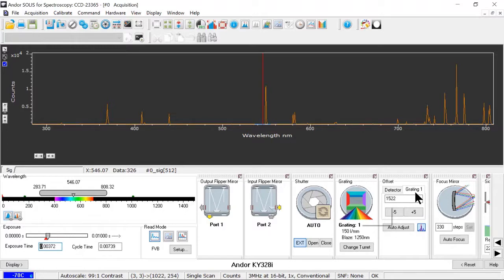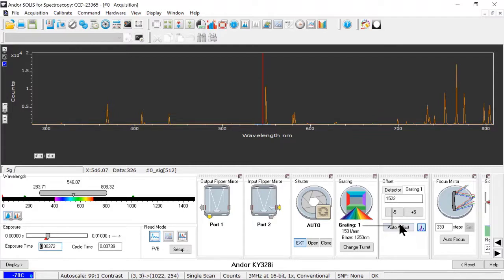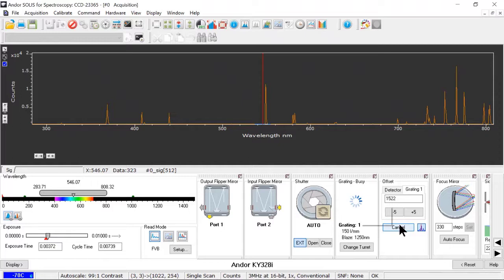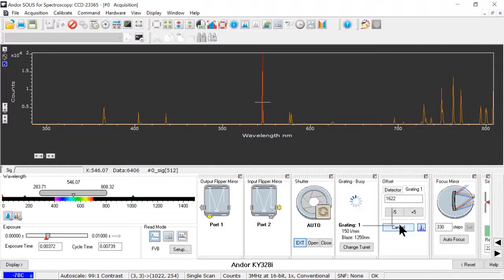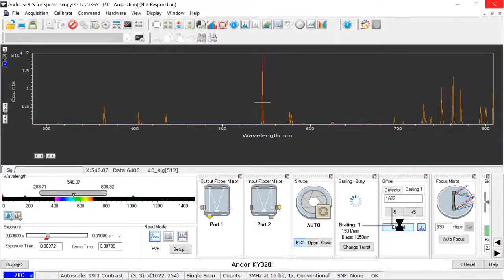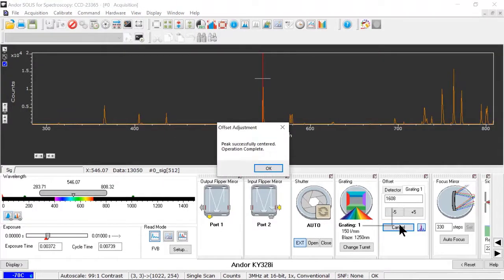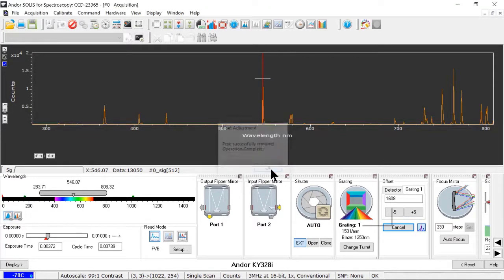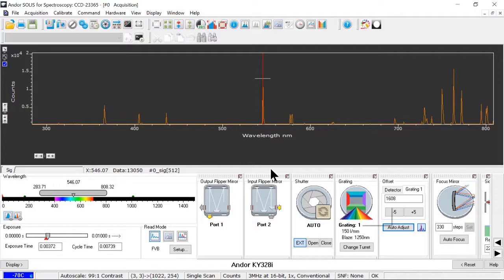So I can either do that manually, or I can do that using our auto-adjust feature. Each individual grating has its own offset that I'll calibrate against, and the detectors have their own offset as well. So all I need to do here is auto-adjust, and the grating and the spectrometer and the camera will work together to move that to the center of the field of view. And we're successful. Now that it's back on, I'm calibrated. There are more ways that you can go deeper with calibration that might even be application-specific. So again, if you have questions, feel free to contact one of us or visit our website for more info.